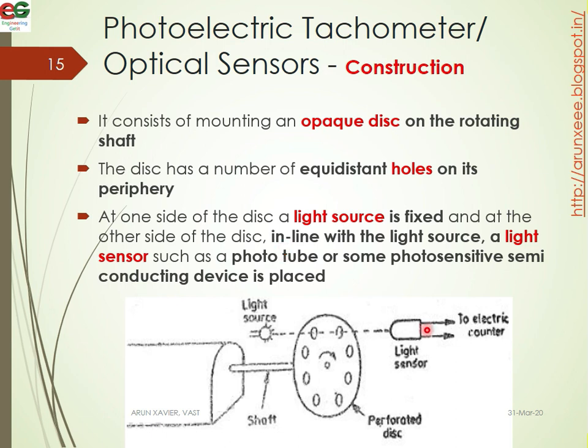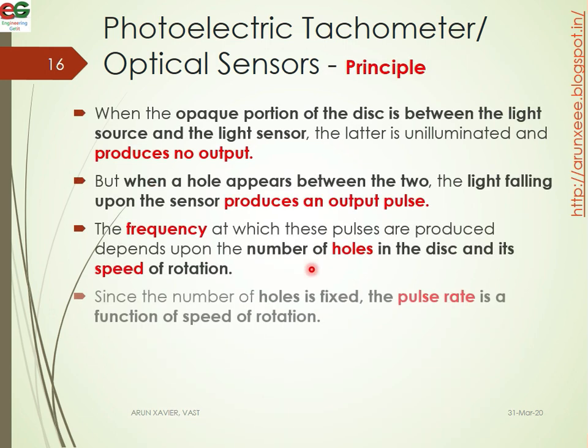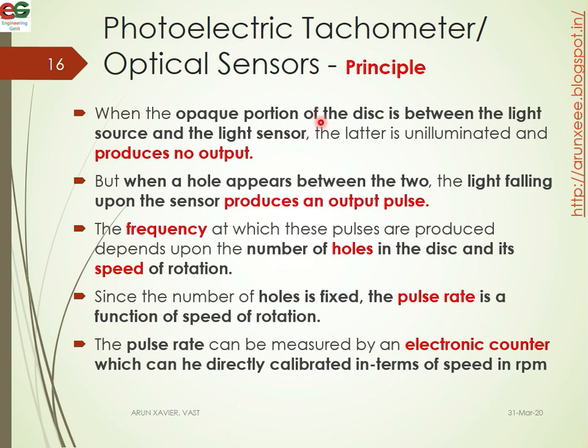On the other side we use a light sensor aligned with the light source. The light sensors are photosensitive semiconductor devices like photodiodes or phototransistors. When the disc rotates, the holes allow light to pass, generating pulses as output. The frequency depends upon the number of holes in the disc and the speed of rotation. Since the number of holes is fixed, the pulse rate is mainly a function of the speed of rotation.